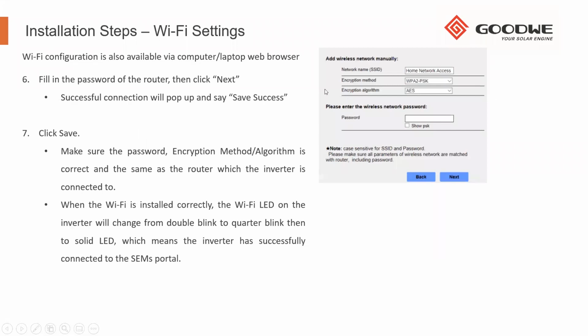You'll see it will then open up this page where we can type in the wireless network password. With the network password and all that, we just need to make sure that essentially one main character that does interfere with the connection is a blank space. So very often people might put a blank space like "my space home". That blank space isn't fully recognized by the inverter itself. So the inverter may connect to the customer's network, but it won't be able to broadcast outwards should there be a blank space. Sometimes a blank space in the network SSID can cause this as well.